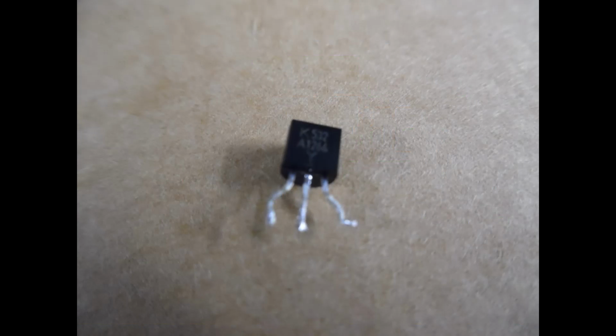Quite an interesting repair, I would say. What I'd mention is that unless you have this component tester, this is going to be a difficult fault to diagnose. You know there's an issue with the DC offset adjustment, so you can focus in on that area of the circuit.